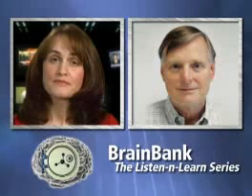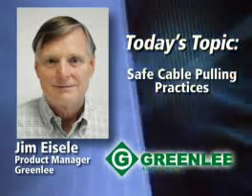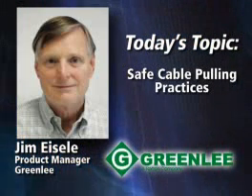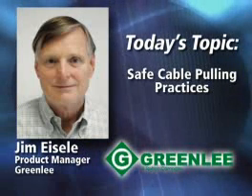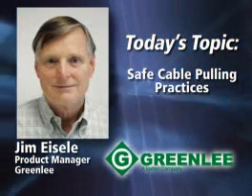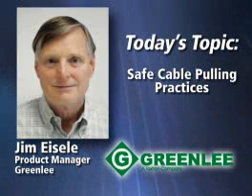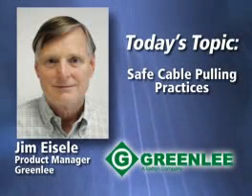Well, I think the only thing I would really like to emphasize is that we see a lot of cable pulls where people are using sheaves and other accessories attached to building parts that just don't have the capability of withstanding the force of the cable pull. And electricians and contractors should follow instruction manuals for these items to make sure that they're attaching them to a structure that's going to withstand the force of the cable pull.